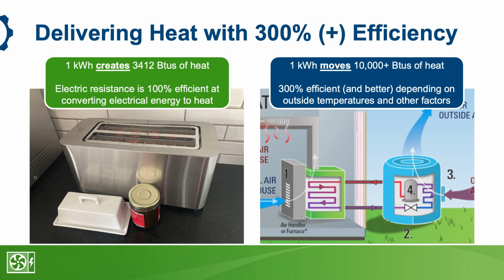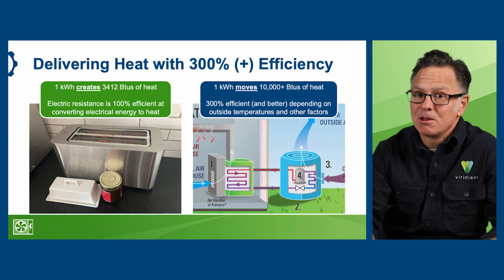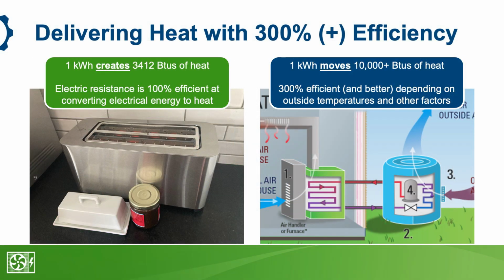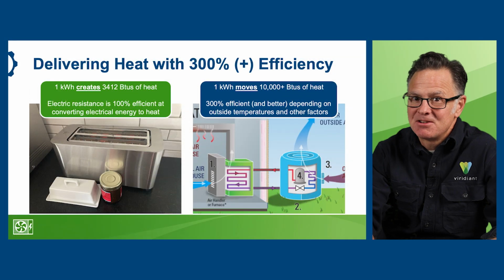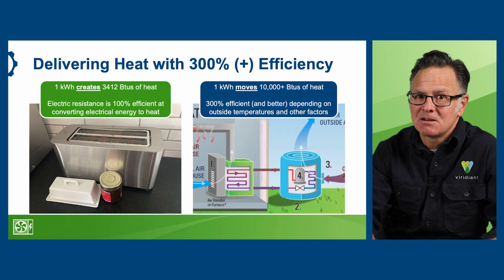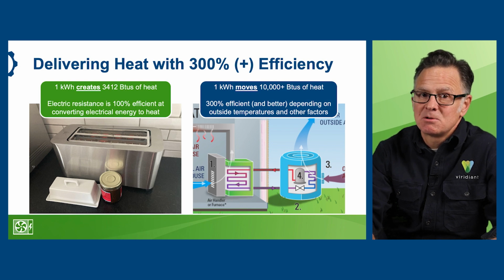But by moving or pumping heat, a kilowatt hour of electricity used by a heat pump can deliver more than 10,000 BTUs of heat to a building. This is why we refer to heat pumps as more than 100% efficient at heating your home or business. The precise efficiency depends on outside temperatures and the performance specs of the heat pump. So, 300% efficient isn't a typo, and it isn't magic. It's actually the same basic refrigerant cycle technology we've used for well over 100 years, just with the most modern equipment.